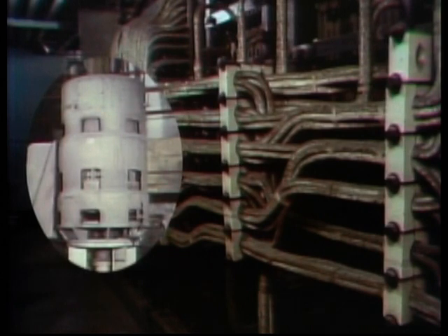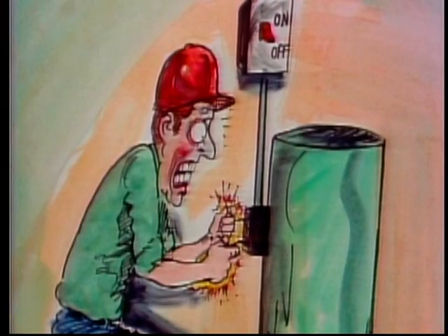But I'm getting ahead of myself. Let's begin with capacitance. Capacitance is the physical property of all AC circuits that opposes a change in voltage. Because capacitance opposes a change in voltage, it has some effects that you should be aware of. For example, the capacitance in high voltage motors and distribution cables causes these motors and cables to store up energy. That stored up energy doesn't go away every time you turn off the power. So if you go to work on a motor that has had its power turned off, you still might get a shock from the stored energy unless you discharge that energy first.